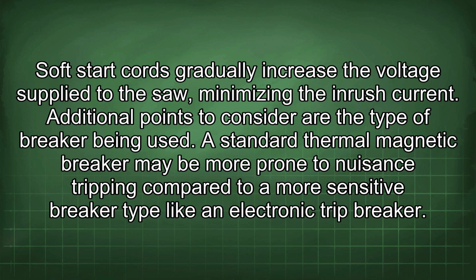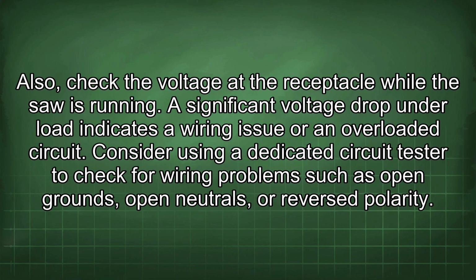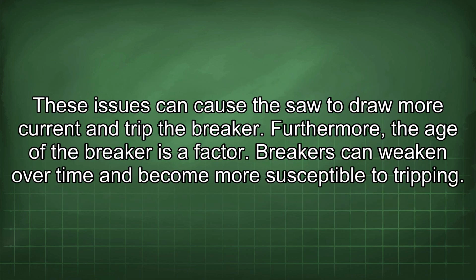Additional points to consider are the type of breaker being used. A standard thermal magnetic breaker may be more prone to nuisance tripping compared to a more sensitive breaker type like an electronic trip breaker. Also, check the voltage at the receptacle while the saw is running. A significant voltage drop under load indicates a wiring issue or an overloaded circuit. Consider using a dedicated circuit tester to check for wiring problems such as open grounds, open neutrals, or reversed polarity. These issues can cause the saw to draw more current and trip the breaker.